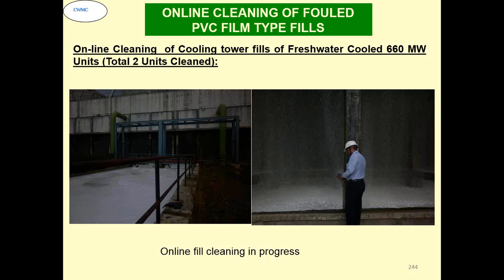Then for freshwater fills, we have done 2 units. Again, the second time the cleaning has been done. This was the cleaning process. What you see, the foam is generated because of that, and that is what takes out the dirt after putting the biocide there. So that removes the biological fouling, and the surfactant removes the dirt from the system.